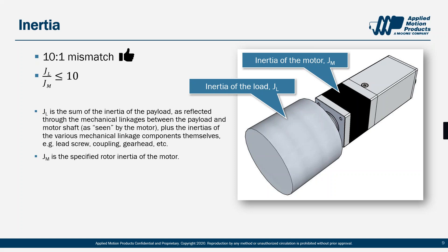In terms of inertia, we want the ratio of total load inertia to motor inertia — commonly called the inertia mismatch — to be no more than 10 to 1. Staying within that 10 to 1 range makes life easier: the motor can accurately control the load during acceleration, deceleration, and while holding position, and you'll avoid difficulty tuning the system or handling the load during maximum deceleration. Essentially, stay within 10 to 1 and life will be good.